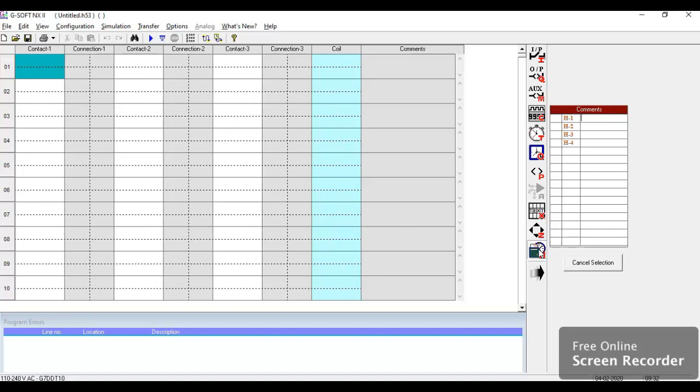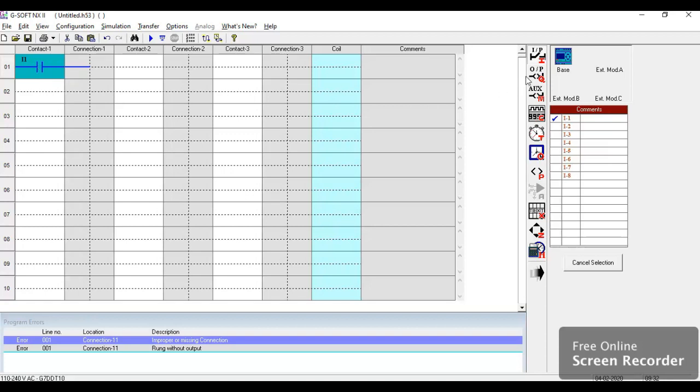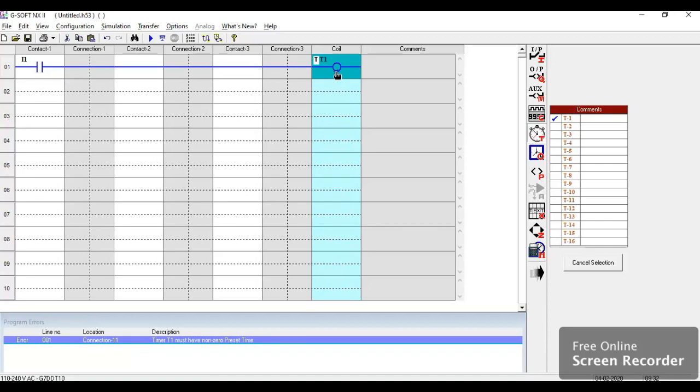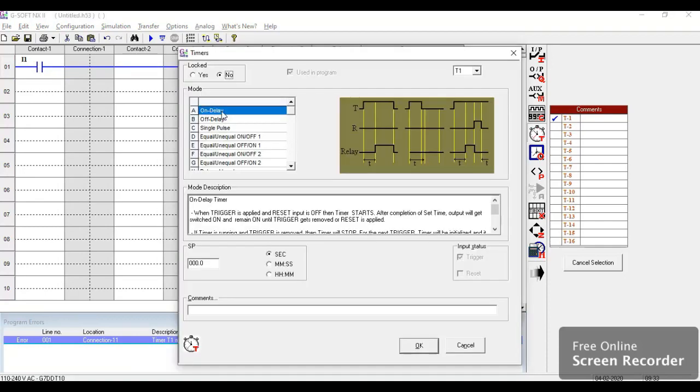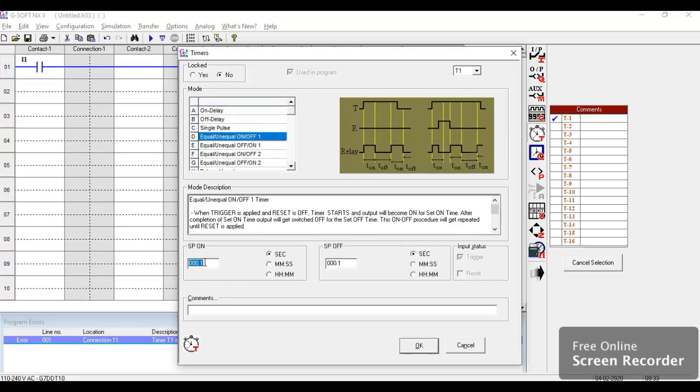So let us do a simple program here by taking one input. We are taking this I1, just drag and drop it here, and we will connect one timer here. This timer T1 will be connected to the input. The coil of T1 is connected to the input right now. We can configure it as on delay, off delay, single pulse, equal, unequal, on off.